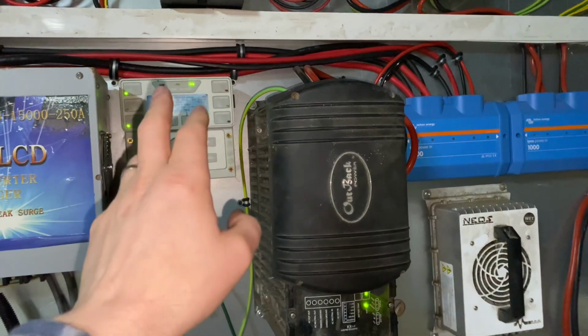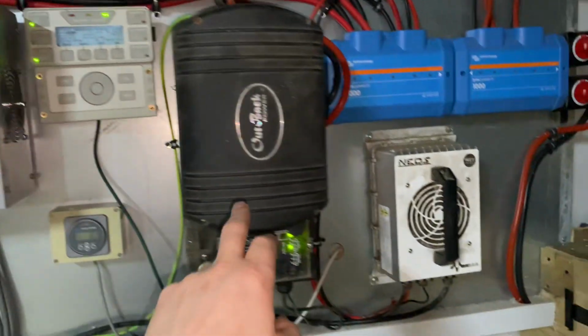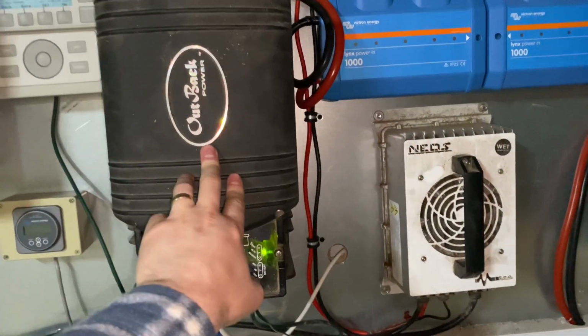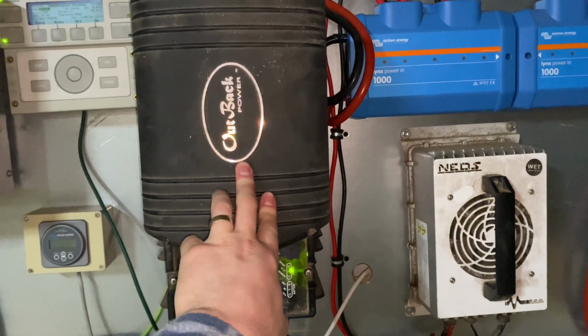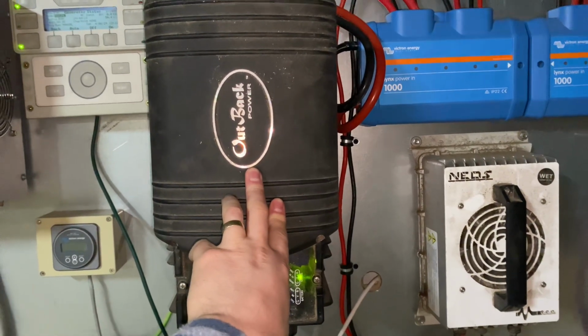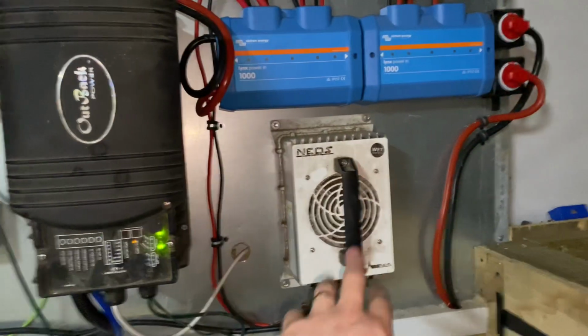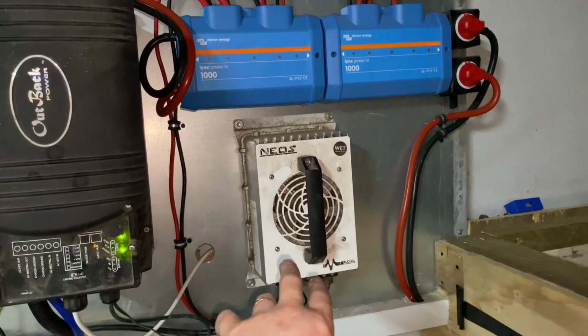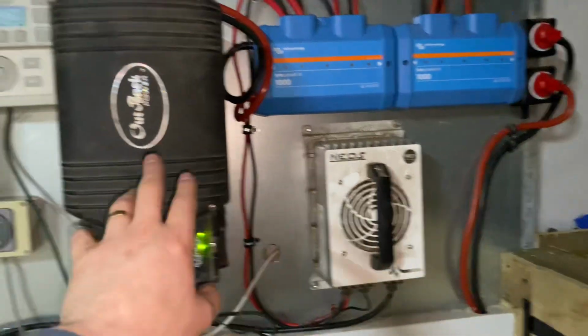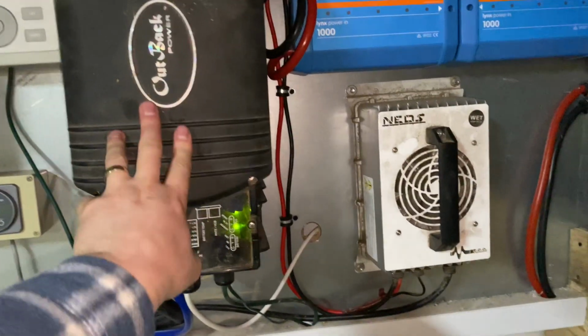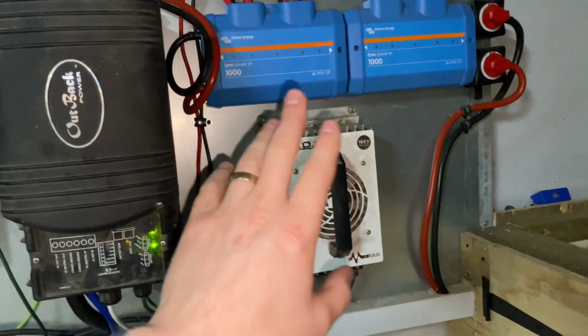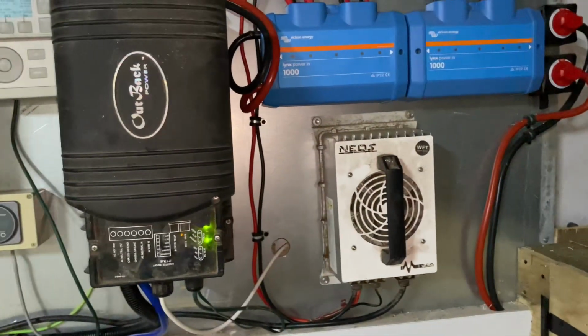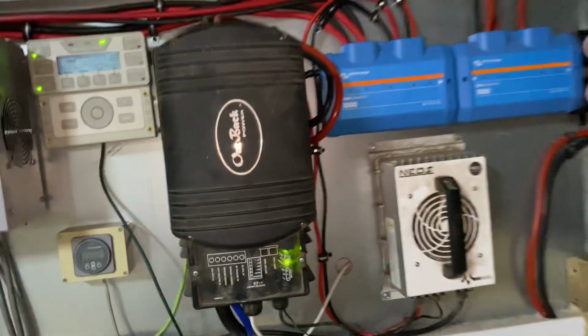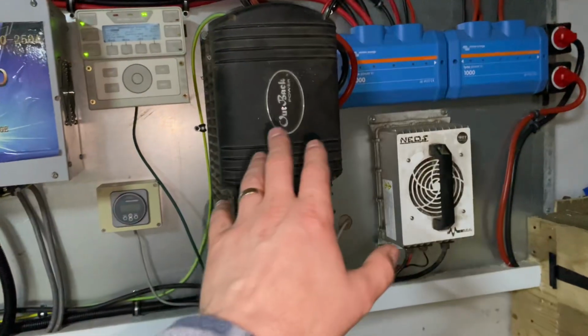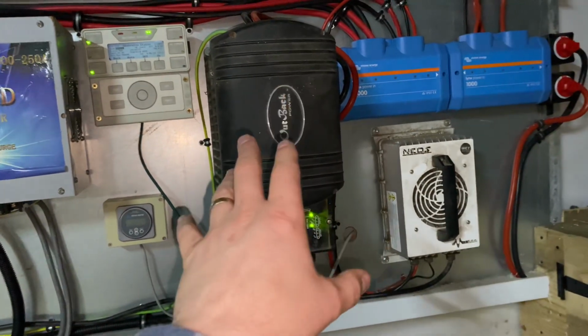But when the generator turns on, this is charging the batteries, and we've got an 8 kVA generator and this charges at about 2,500–3,000 watts. But I've coupled up another 50 amp forklift battery charger. So when this turns the generator on, this will charge the batteries and so will that. So the generator will only run for about 45 minutes at a time, just so it's not running all day. So this is an inverter charger, very old, reliable system.